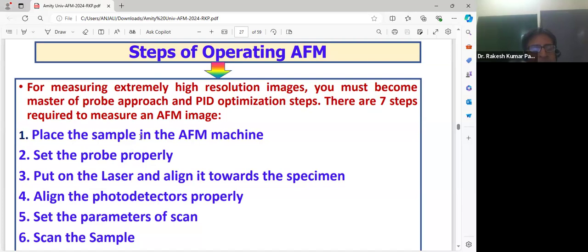First of all, place the sample on the AFM stage. The placement of your sample should be appropriate. If the placement of the sample is not appropriate, there will be no proper focusing of the laser beam. So this is the first step: place the specimen at the proper place, and set the probe properly. It is very important. In the third step, turn on the laser and align it towards the specimen.